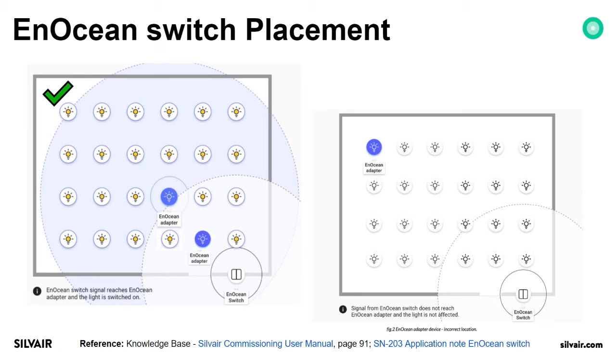For redundancy, on the left side, you can see the node which has the connectivity with an EnOcean switch should be in very close proximity to such an EnOcean switch. The radio on an EnOcean switch is very low in range. So always try to use devices as close as possible.